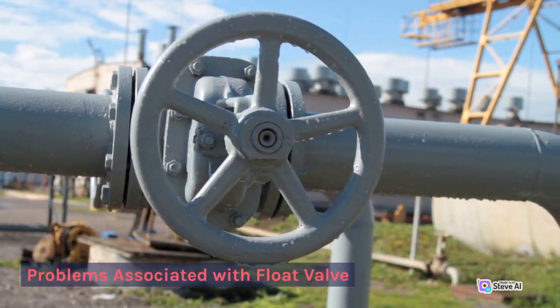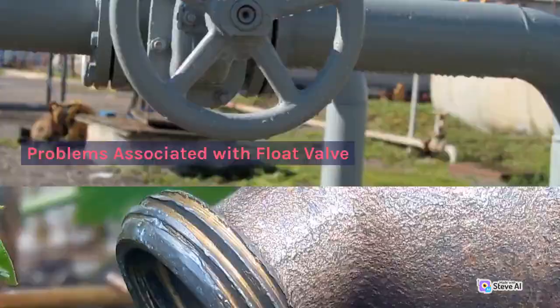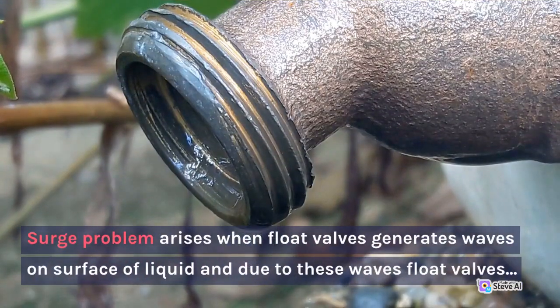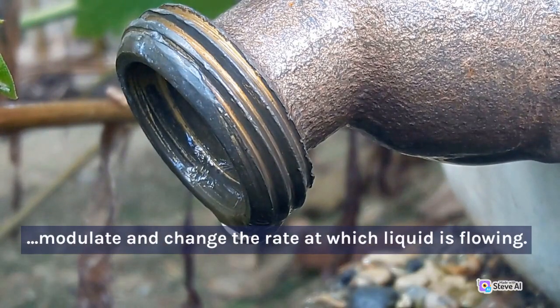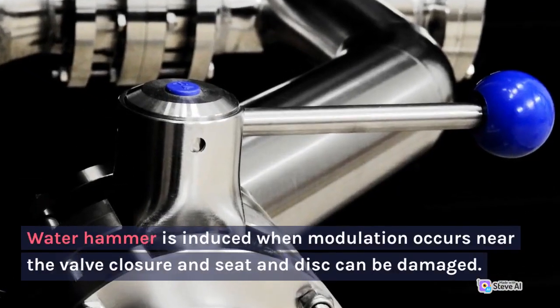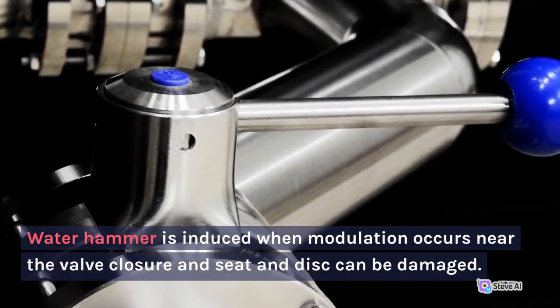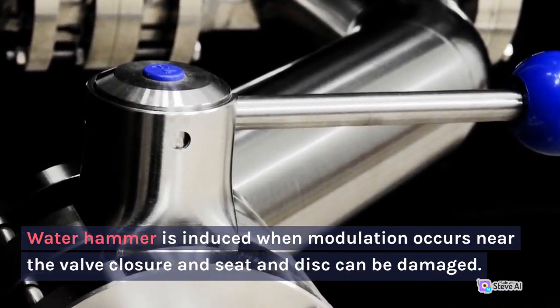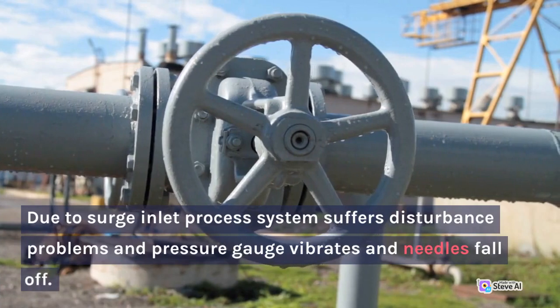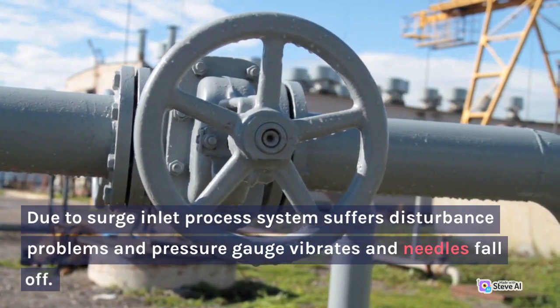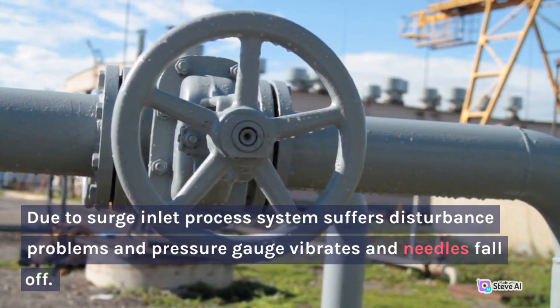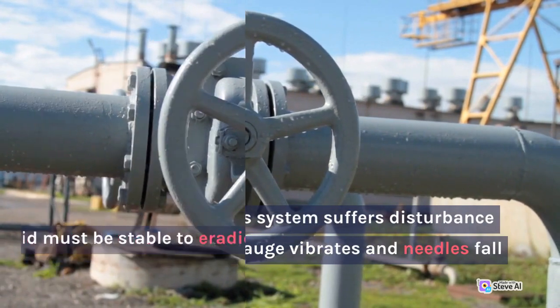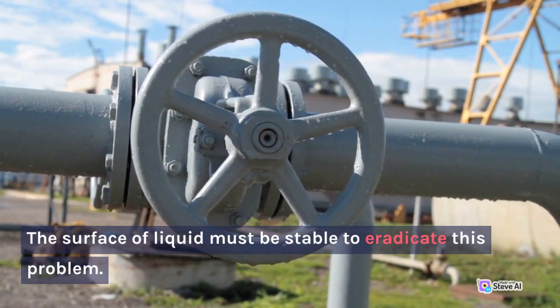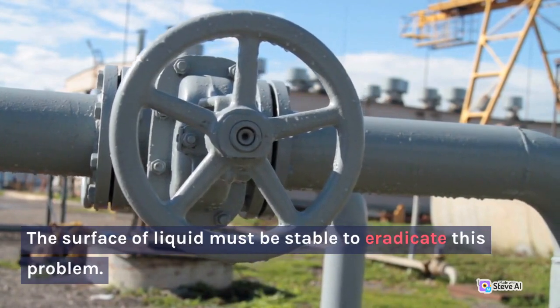Problems associated with float valve. Surge problem arises when float valves generate waves on the surface of liquid, and due to these waves, float valves modulate and change the rate at which liquid is flowing. Water hammer is induced when modulation occurs near the valve closure, and the seat and disc can be damaged. Due to surge, the inlet process system suffers disturbance problems and the pressure gauge vibrates and needles fall off. The surface of liquid must be stable to eradicate this problem.